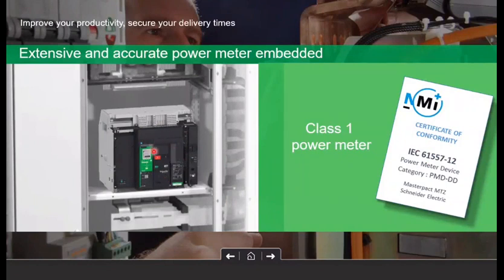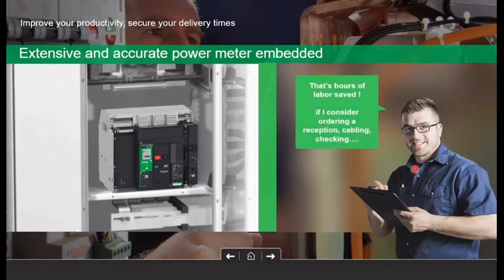If you see the values MTZ is giving you, you don't need external CTs, external accessories, or external meters. You will get all the CTs, all the accessories, all the metering by default in the breaker. If you go for a meter with Ethernet connectivity, a basic meter with Ethernet connectivity will charge you 7 to 8,000. The CT will be extra, and the recurring cost of calibration and the cost of downtime will again be extra. Here in MTZ you will get class 1 energy accuracy, THDI and THDV by default, class 0.5 accuracy for current and voltage with Ethernet connectivity, again in compliance with IEC 61557-12. So we can save a lot here by using this accurate and inbuilt power metering feature of the Masterpact MTZ ACB.